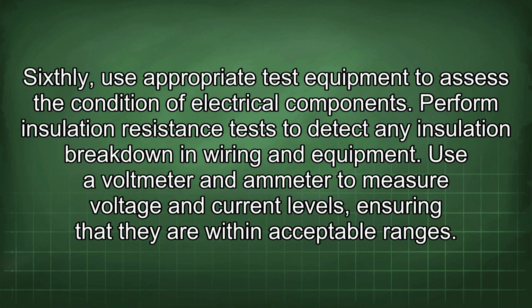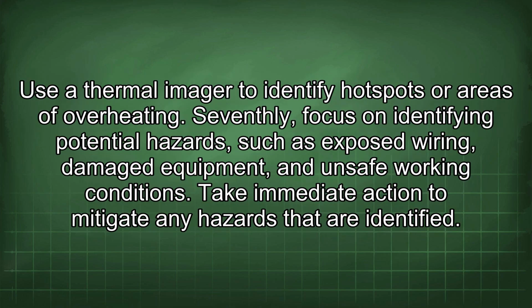Sixthly, use appropriate test equipment to assess the condition of electrical components. Perform insulation resistance tests to detect any insulation breakdown in wiring and equipment. Use a voltmeter and ammeter to measure voltage and current levels, ensuring that they are within acceptable ranges. Use a thermal imager to identify hotspots or areas of overheating.